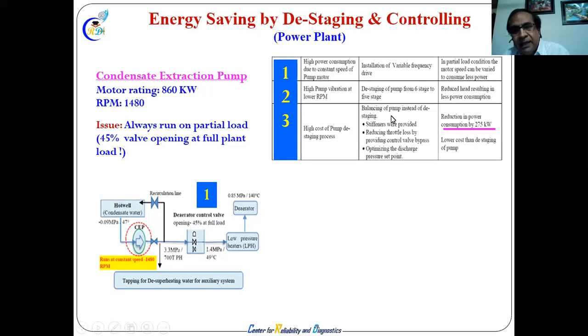So accordingly they made some changes in the structural plates and other things and material, all the things they have done. So in different cases, in 2-3 stages they got the benefit, and that benefit was 275 kilowatt. On a lighter side, this benefit is the cost of not selecting the right pump initially. So nothing to blame. They are getting this much less right now. Otherwise, they would use this machine, and this machine would create so much energy loss, more than 50% energy loss. So they have got this gain.